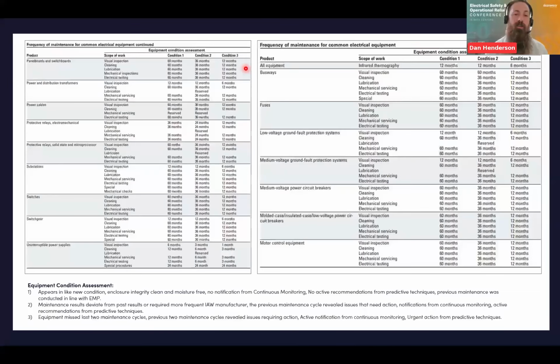So in theory, your kit might have been brand new day 1. So you've gone, I've done my initial condition assessment, and this is a 60 months approach that I'm taking. It's condition 1, but for whatever reason, operations, life gets in the way. You can't get the shutdown, so then it drops into condition 2. You try and do your 12 monthlies. So potentially this equipment might not have been actually maintained for over 8 years by the point you actually get into condition 3. So it becomes this 12-monthly item to then jog, push it up the urgency to try and get you to shut it down to then do your maintenance.